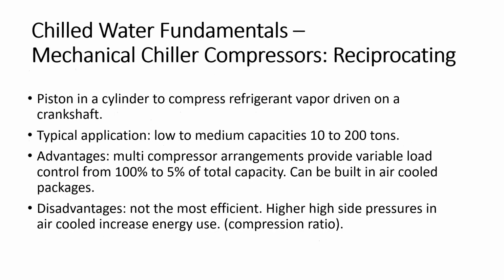Okay, so we're going to talk a little bit about compressors. Each one of these compressors has its own characteristics. The most fundamental is the reciprocating, and we talked about that when we looked at the air-cooled. You see a lot of these in low to medium capacities, 10 to 200 tons in a package. The advantages are that you can have multiples arranged to control your varying capacity. So from 100% all the way down to 5% of the total capacity, it can be built in an air-cooled package, shipped to the site. All you got to do is pipe up to it, fill it up with water, run the pump, and hook it up to electricity, and you're good.